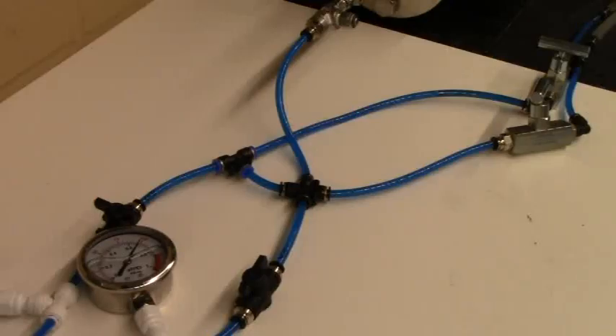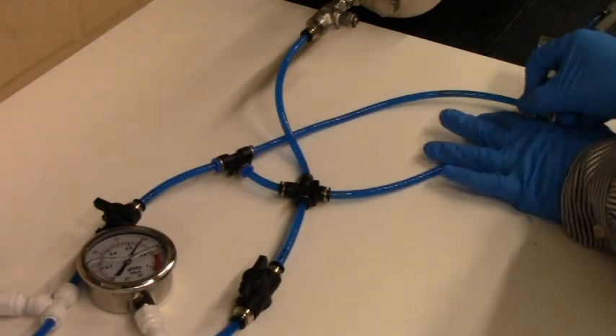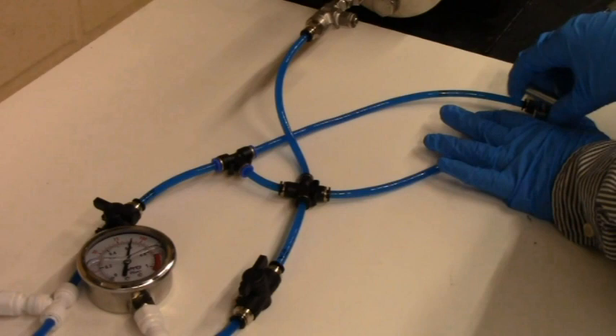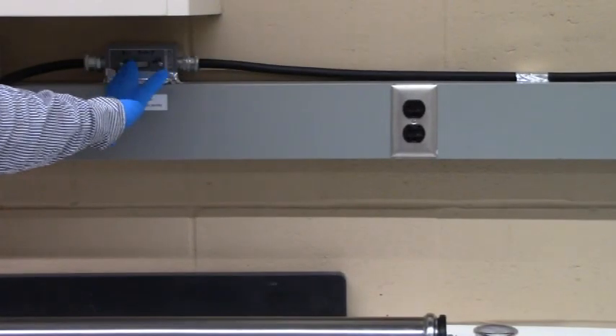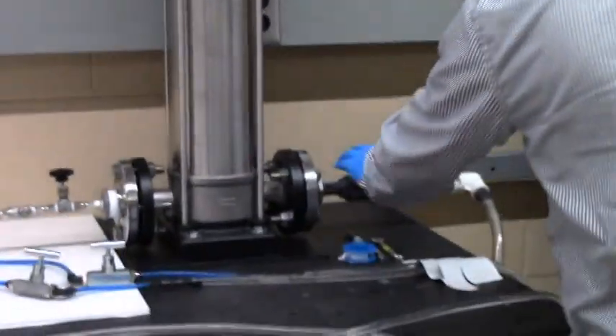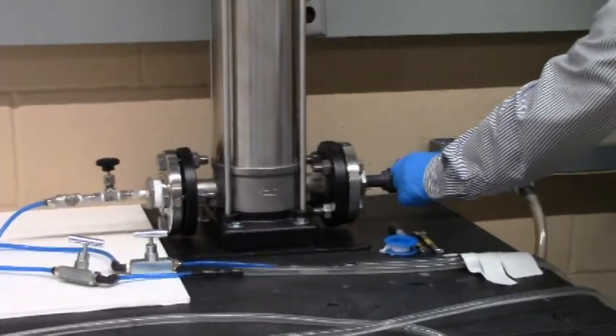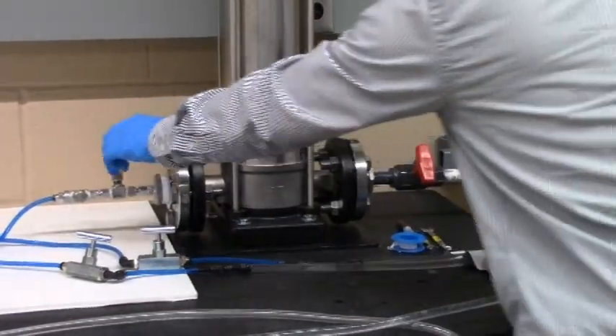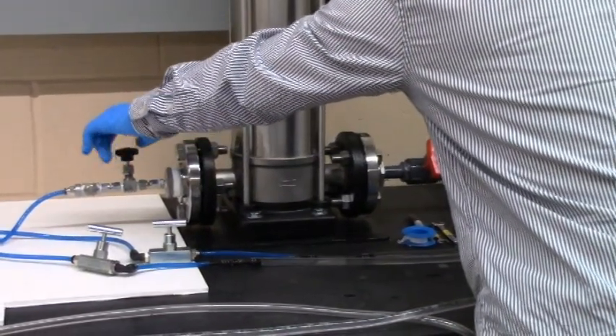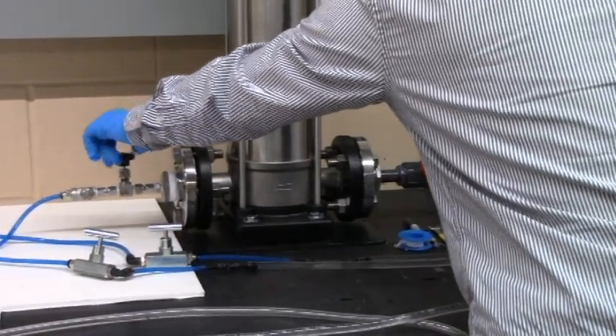Throughout the data collection, monitor the inlet pressure as it tends to creep up. Do not exceed 100 psi. Turn off the centrifugal pump by flipping the switch. Close the pump suction valve and then discharge valve. Finally, plug off the electrical cord from the wall outlet.